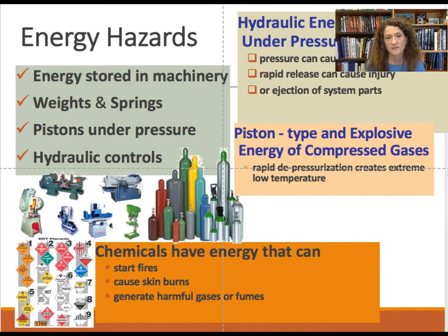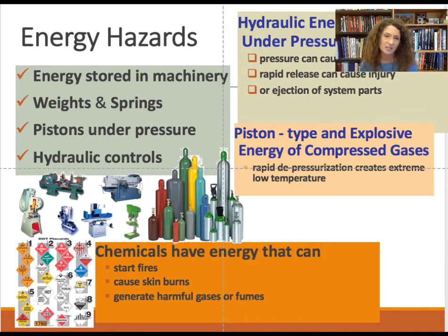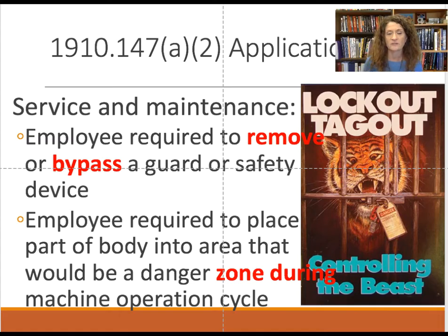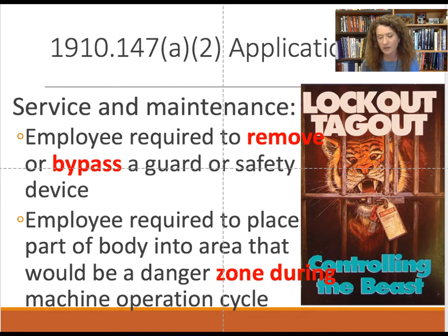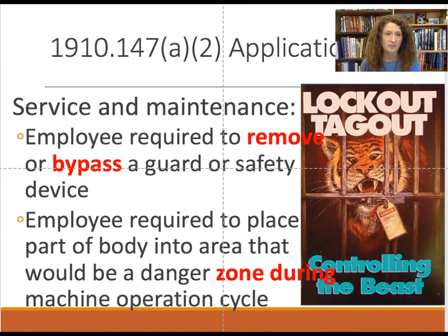Different kinds of energy sources to identify include energy stored inside a machine — such as machines with weights, springs, or pistons under pressure — which must be released so it doesn't injure someone. Chemical hazards can start fires, cause skin burns, or release harmful gases. Sometimes it's the shutdown or startup process, such as equipment cooling, that causes a release of energy. Always proceed with caution and identify which energy sources need to be isolated.